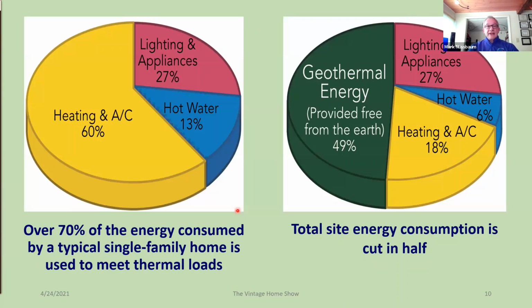So why do we care? Heating and air conditioning in a typical single family house comes in at about 73% of the total energy consumption. When you add the geothermal component, I take almost 50% of the total and provide it from the earth, and now I'm only using 24% electric energy to do the same load. So you're basically cutting in half the amount of energy consumed on site in a typical residence.